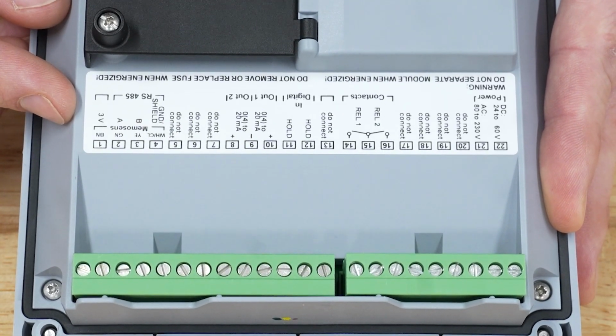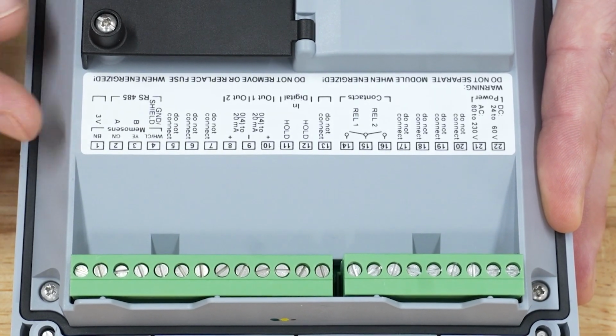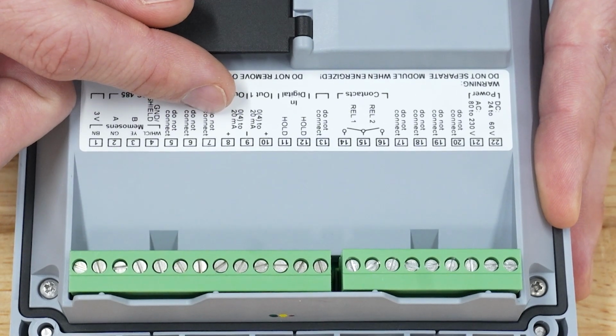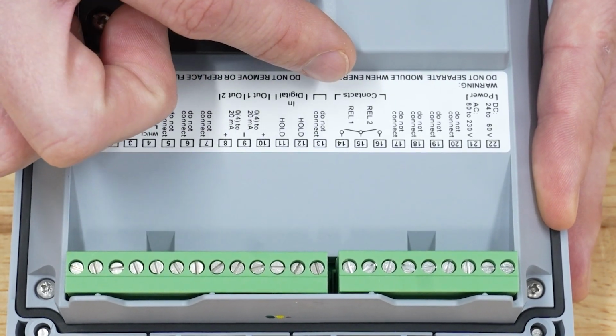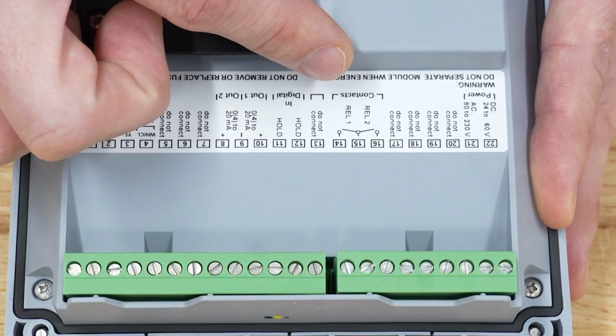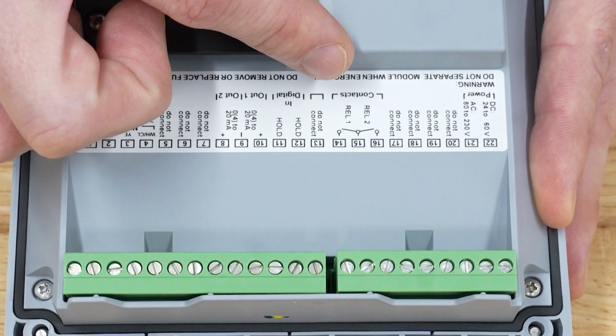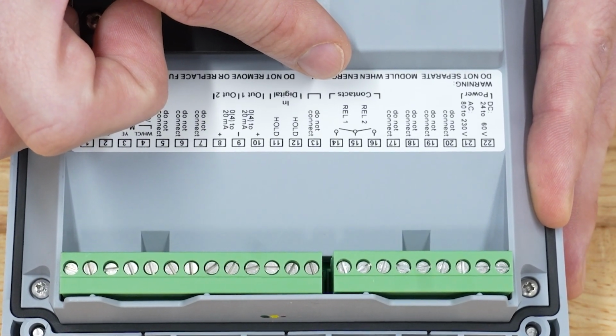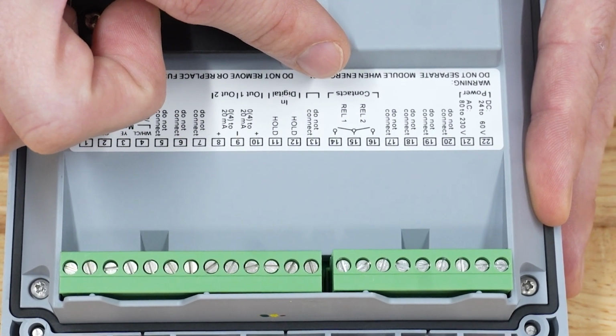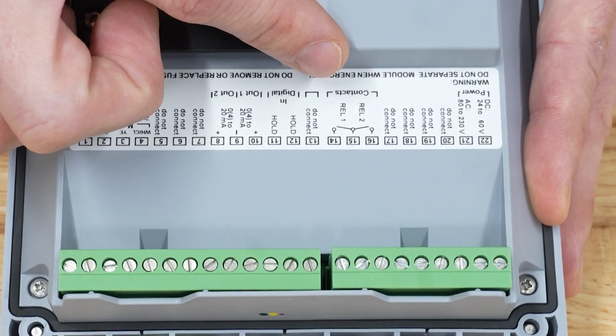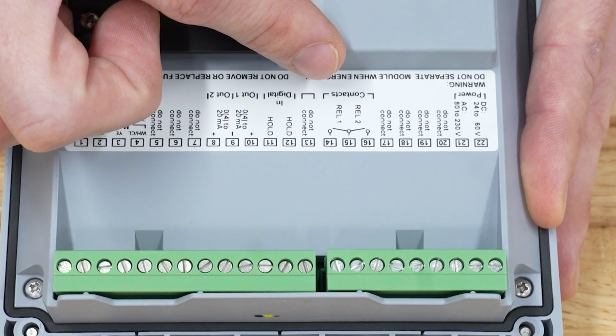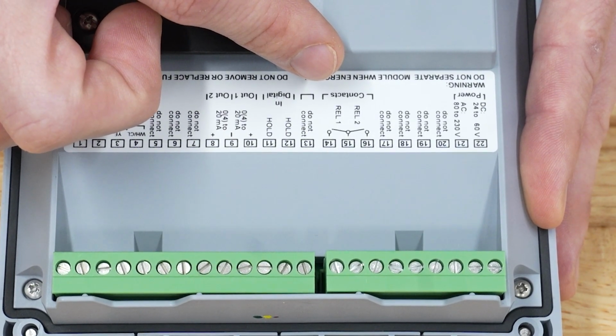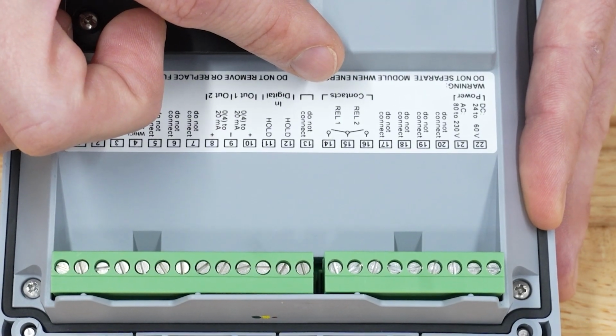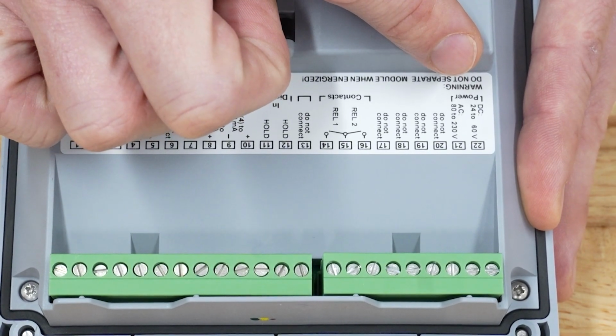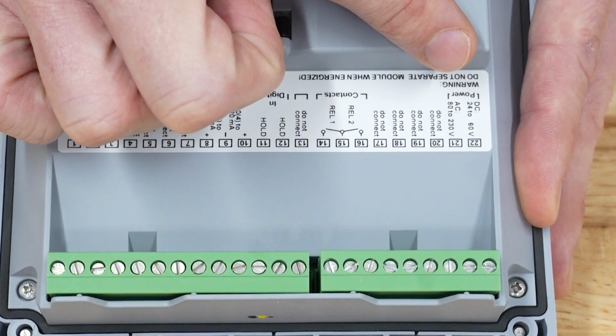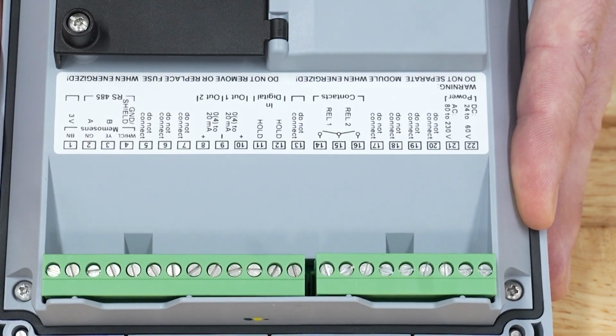sensor input. This device also comes equipped with two 4 to 20 milliamp outputs, as well as two relay contacts, which can be freely configurable for alarms, high-level or low-level values, as well as a wash contact for automatic cleaning of the sensor. Another nice feature of this device is that it is universally powered, so anywhere from 24-volt DC up to 230-volt AC can be used to power the device.